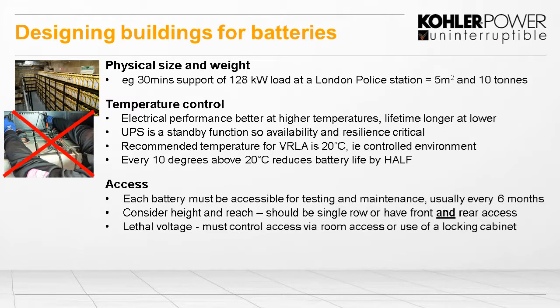Again, another thing that we like to highlight to you is access requirements for batteries. Batteries need to be tested and maintained, typically every 6 months. So when we put them in installation, we have to consider where they are and how easy it is to maintain. We have a picture there of someone leaning across batteries, which isn't good when these batteries can be 500 or 600 volts, and it could be quite lethal. So the access to those batteries also has to be considered, where we put them and how we mount them.